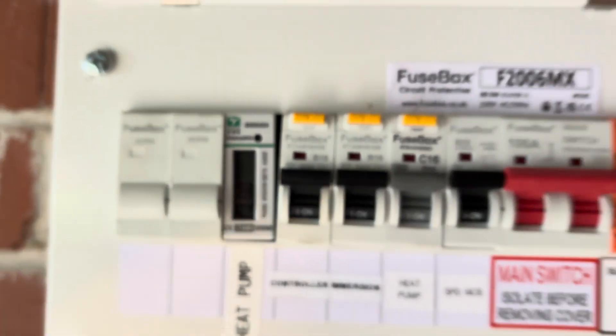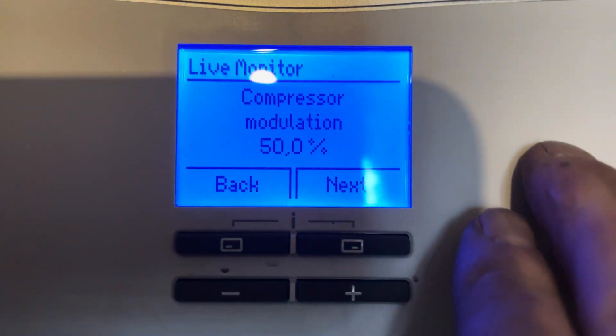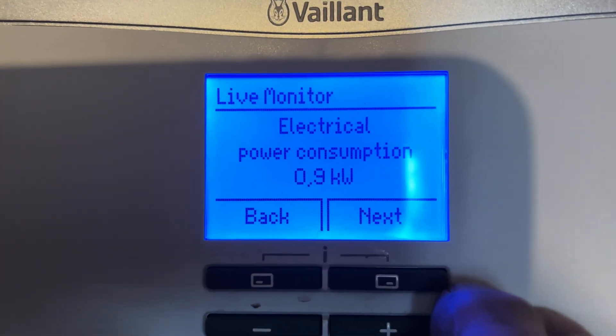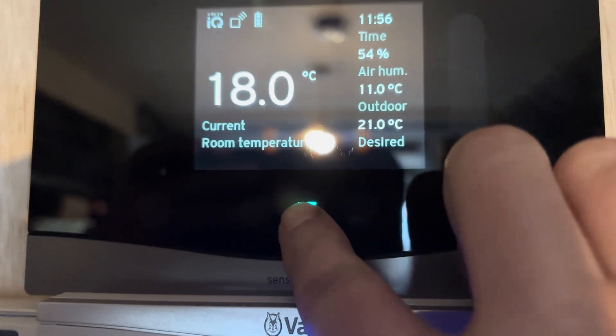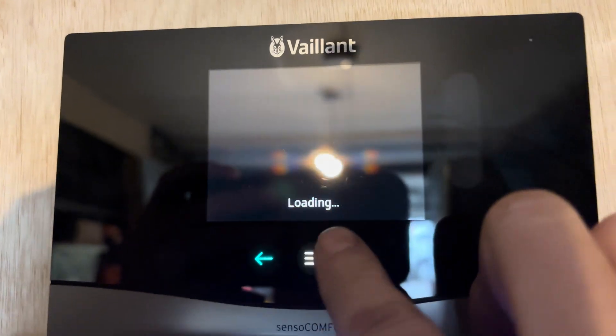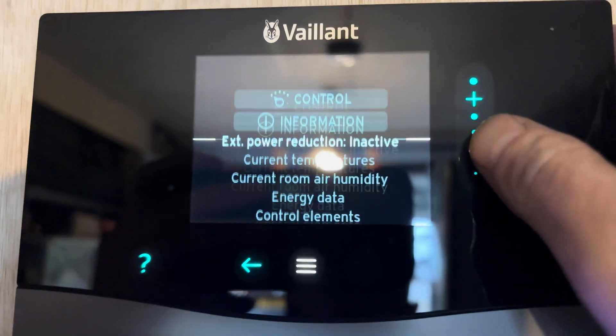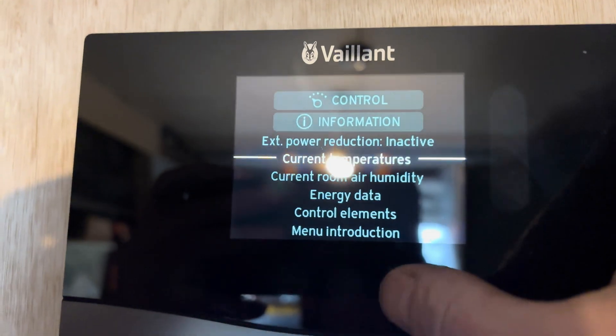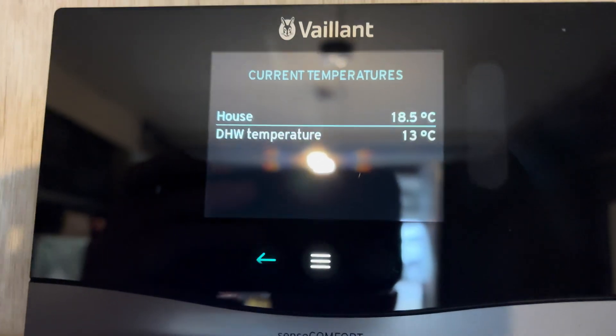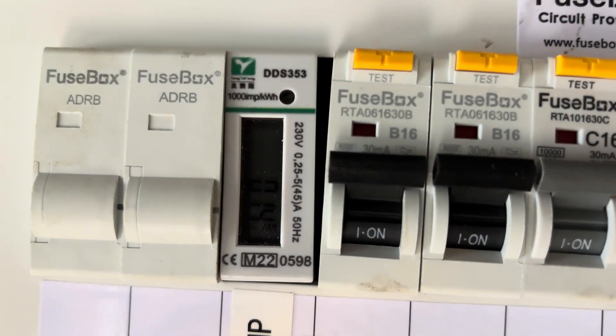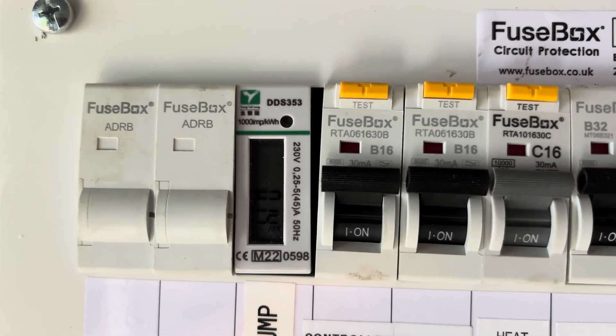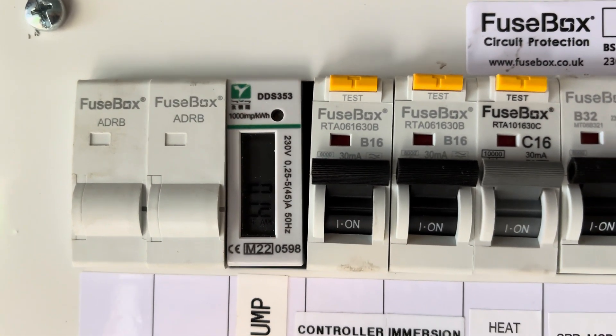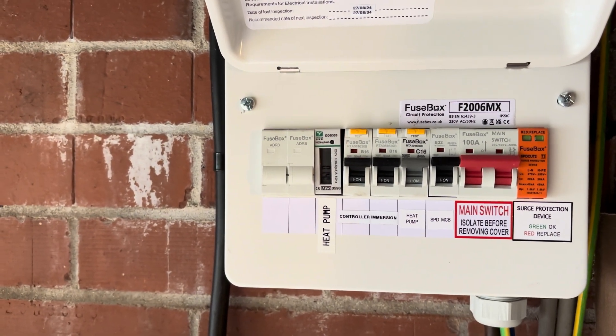Right, 10 minutes in. We can see compressor modulation's at 50%, power's at 900 watts. Cylinder's at 13 degrees C. Let's check the electric meter. We've been running for 10 minutes now and we are 0.14 kilowatts. Gone up 2 degrees C on the temperature.